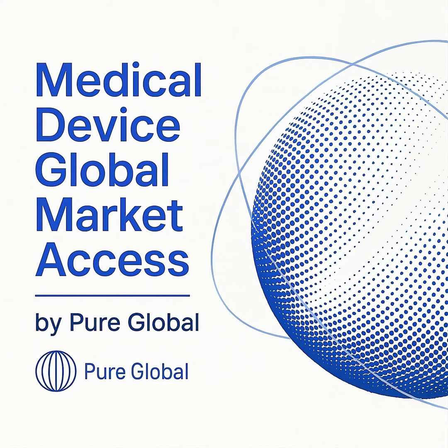You must also include extensive information on design and manufacturing processes, covering everything from raw materials to the final production and quality control procedures. A cornerstone of this documentation is the demonstration of conformity to the General Safety and Performance Requirements, or GSPRs, which replace the essential requirements under the new EU Medical Device Regulation, MDR.